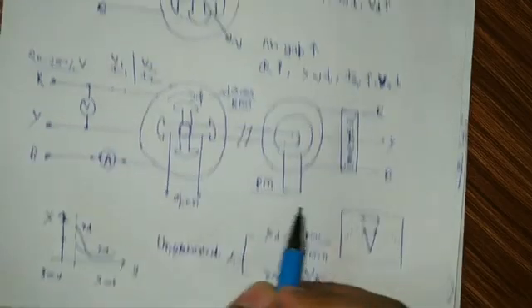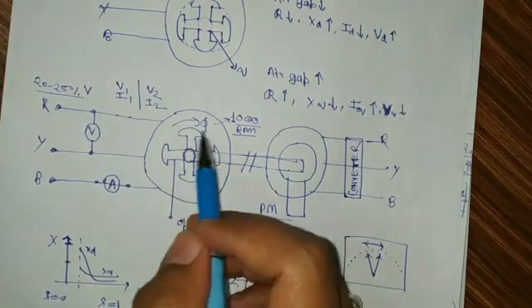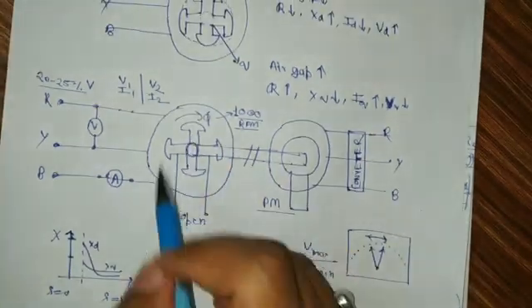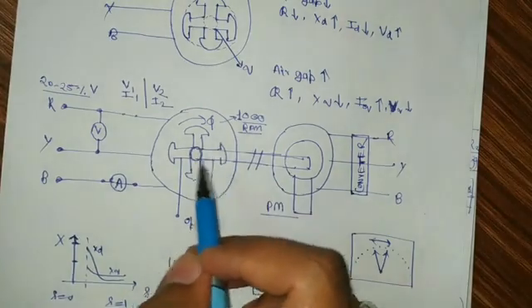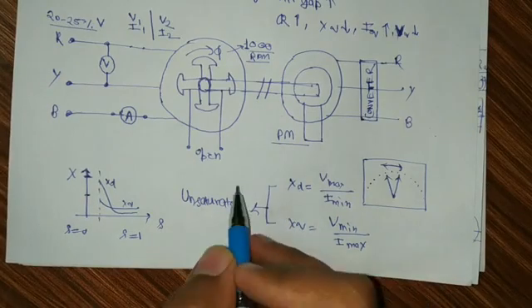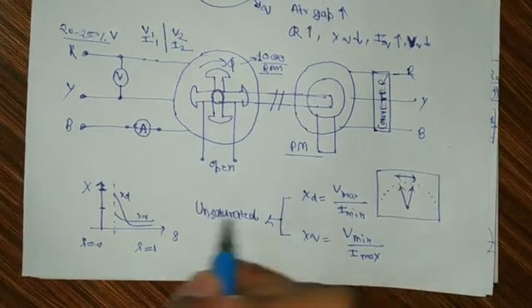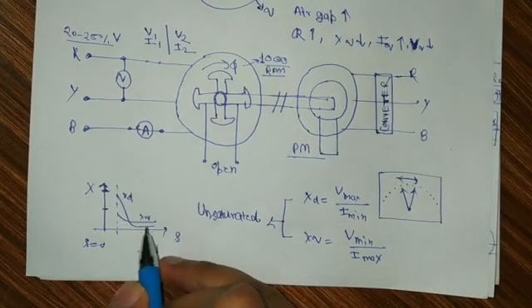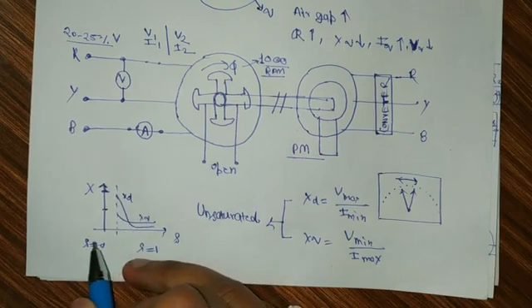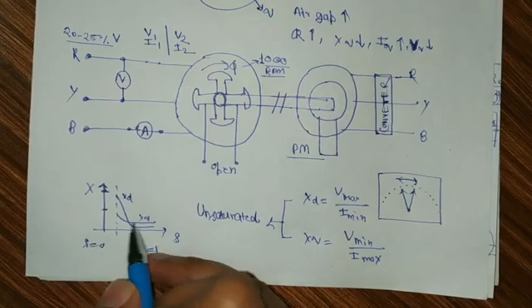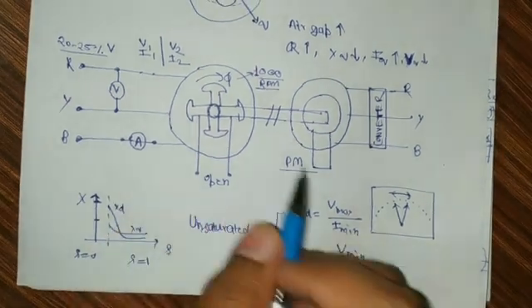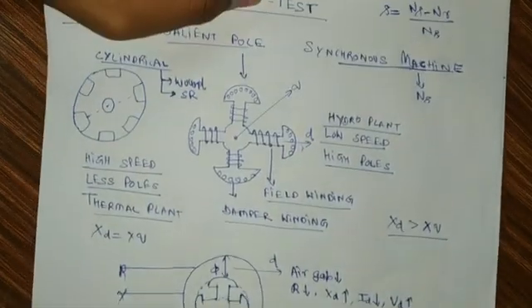These values are obtained when the rotor is running at slip speed, so these values will be unsaturated. Whenever this machine is used in a plant, this rotor will run at synchronous speed, so the reactance will be different. To find the exact unsaturated reactance, we will do a plot between various values of Xd and Xq at different speeds, and at slip equal to zero — meaning at synchronous speed — we can extrapolate this plot and get the exact values of Xd and Xq. This is all about the slip test of a salient pole synchronous machine. Thank you very much.